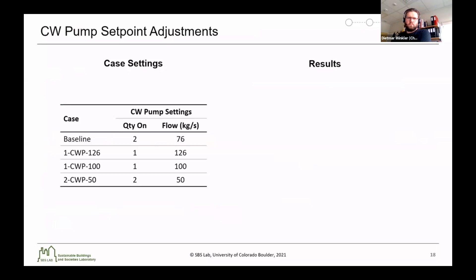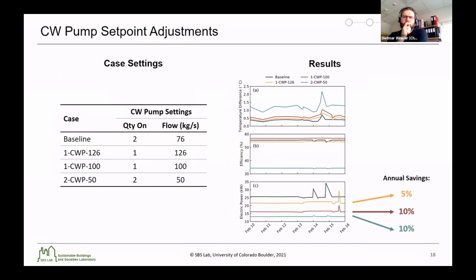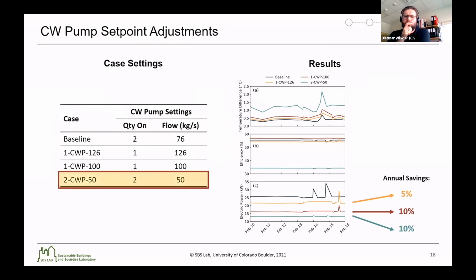Looking at the condenser water pump setpoint adjustments, we ran a variety of cases with different quantities of pumps running at one time and different flow rates. The main takeaways are that different configurations produced different delta T's on the condenser water side, different pump efficiencies, and different electric power consumptions. On an annual basis, the best two cases produced around 10% annual savings, and from these we selected one case for further analysis.